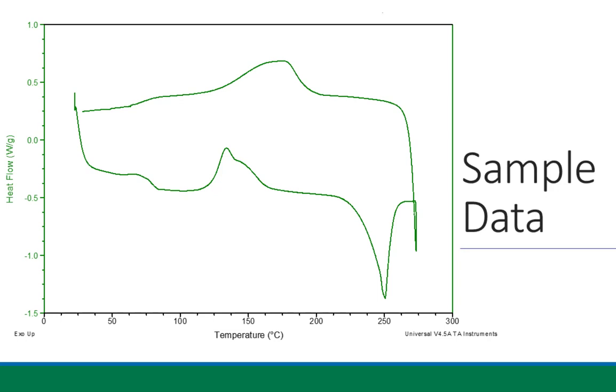In the very bottom left of the plot, you'll see the text 'exo up.' Convention dictates that you indicate which direction is exothermic when plotting DSC data. A positive or negative heat flow value isn't inherently exothermic or endothermic — it depends on the sign convention used. Some plots have the axis flipped with exothermic down. As long as you see 'exo up' on the plot, you can use that to identify which direction is exothermic.